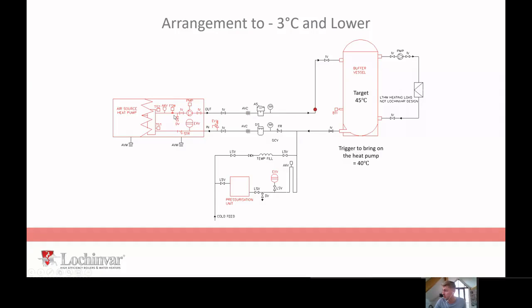So we've got a 45 kilowatt heat pump serving our 400 litre thermal store. We're flowing in at 47 degrees, we're returning at 42 degrees, 5 degrees on the primary. The secondary side of the system would be independent, operating just in the same way a heating system would if it was the secondary side of a low loss header instead of a thermal store. The water is going to go to our various zones, do whatever it needs to do to heat up that building to satisfy the various loads and various zones in that building and keep the occupier warm and happy. So that is a basic application for an air source heat pump.